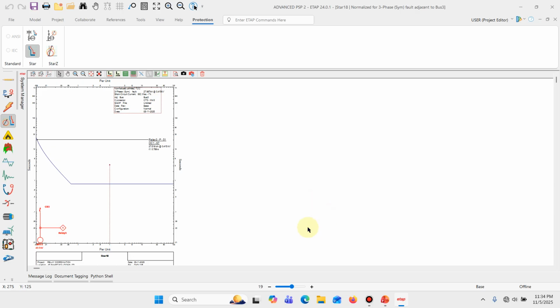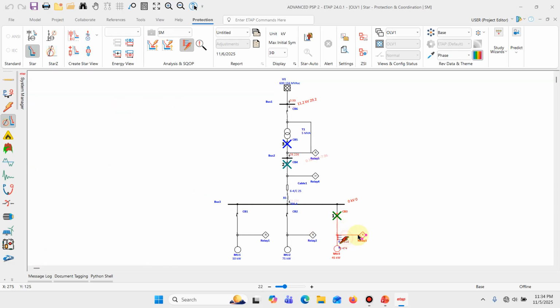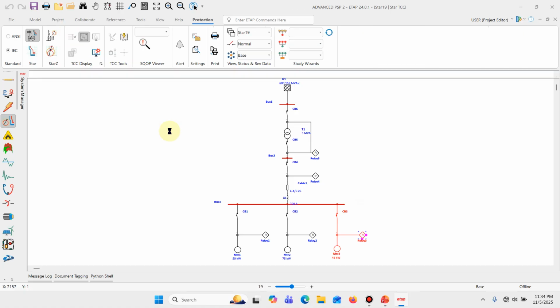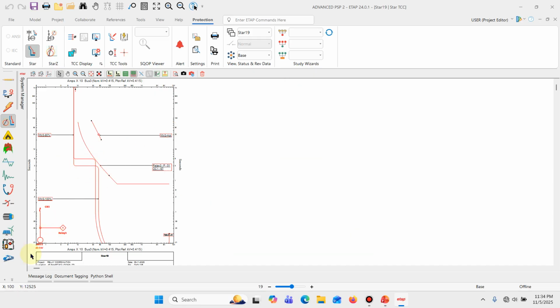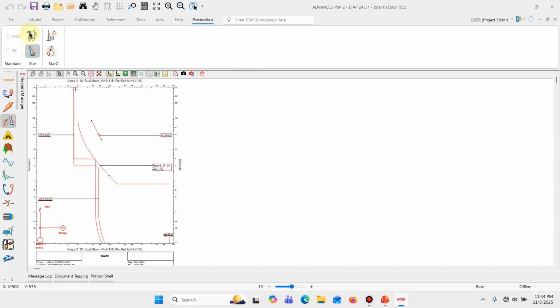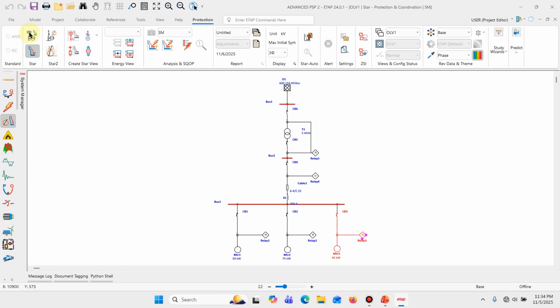Okay, we have a fault inserted on the system, so that's why we are having this. So we can create a star view. Okay, so now we have the motor. This is the motor starting curve, and we can see this is the relay curve. So I'll leave it to you to decide, is this system properly coordinated or not? Is that time of operation too much or too less? Should it be increased or should it be decreased? So in your opinion, is it properly coordinated or not?